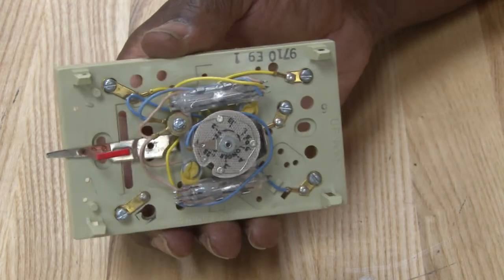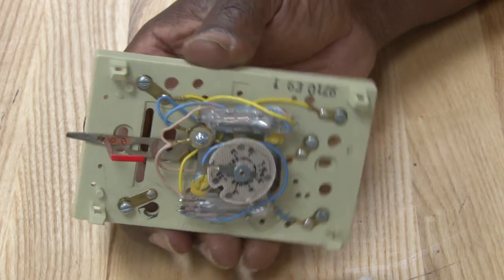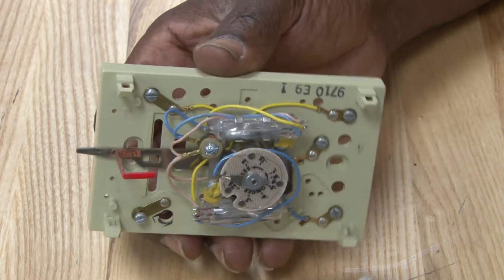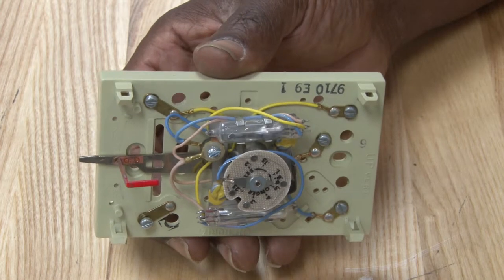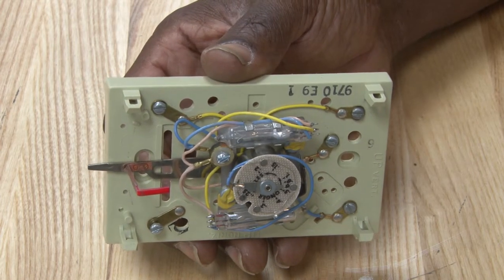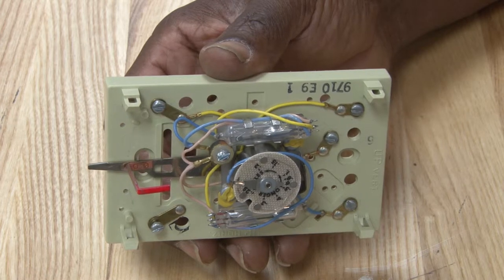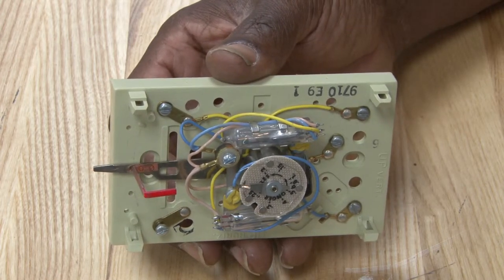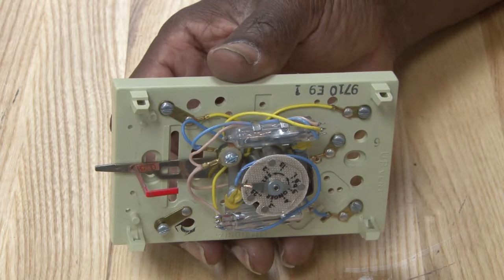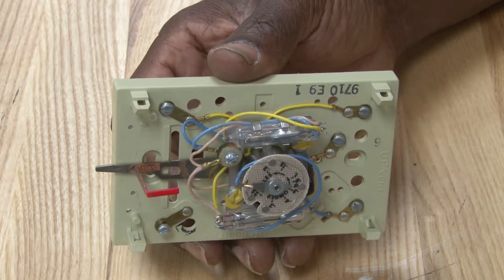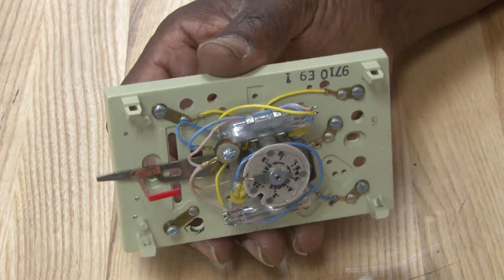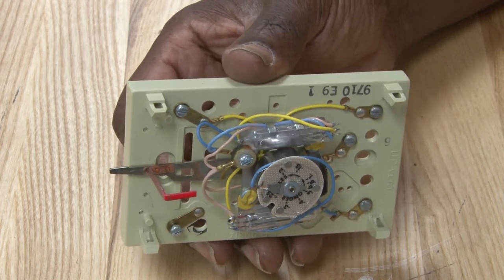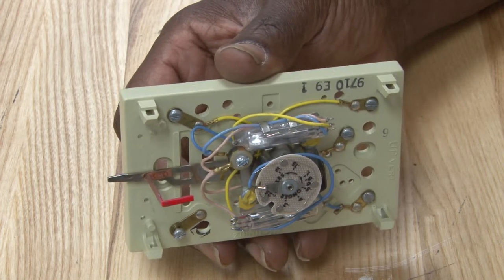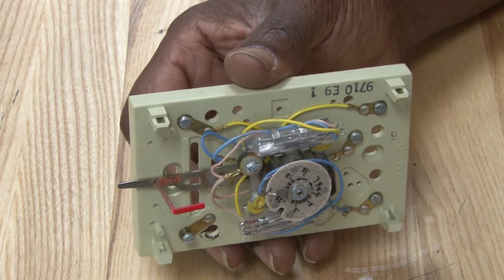Other types of thermostats you may find. This is another type. This is a two-stage thermostat. It has two sensing bulbs. So some larger systems may have two compressors or two furnaces or two elements or a two-stage heating system that will turn on and turn off at different times or different temperatures. So this is a two stage. You can see that the mercury is moving at a different rate. They are slightly out of calibration of each other for that purpose.